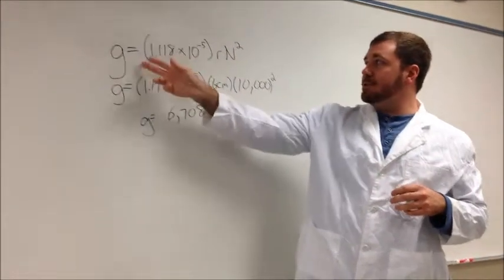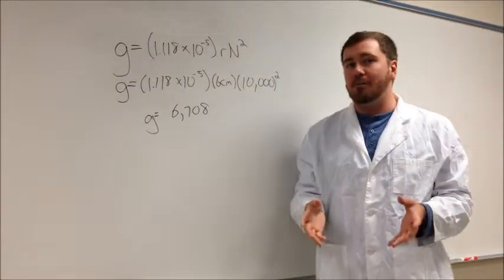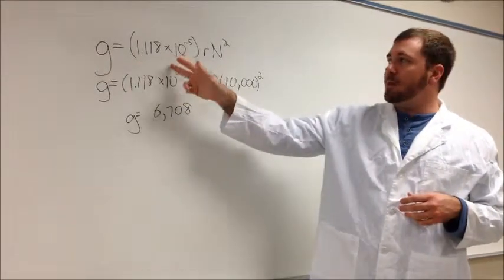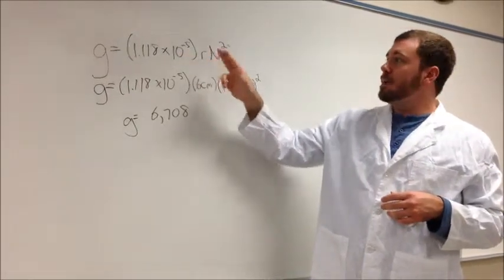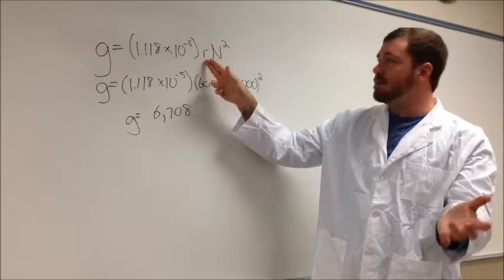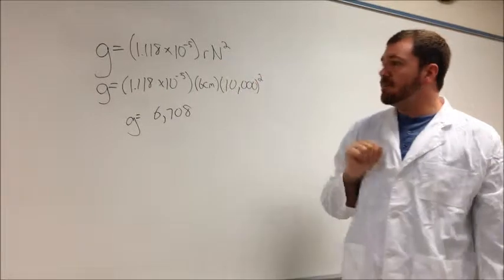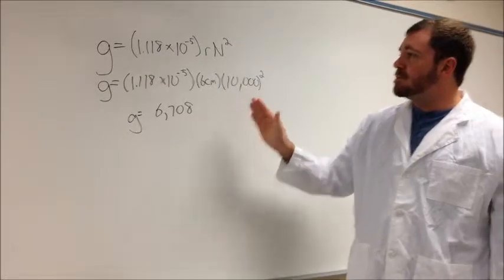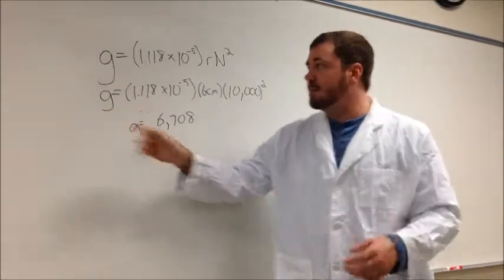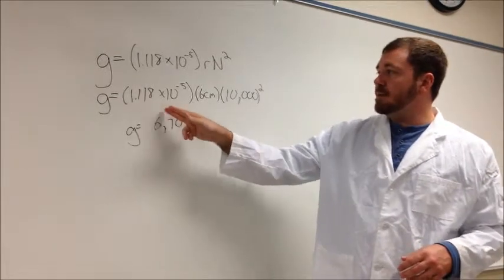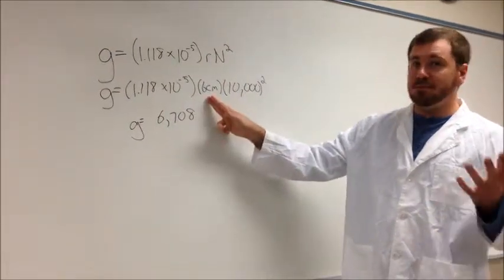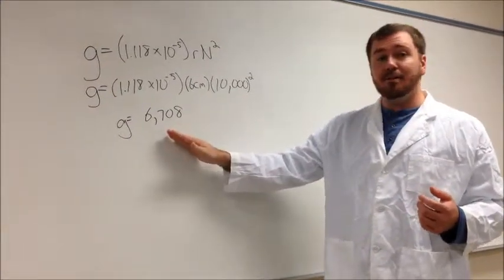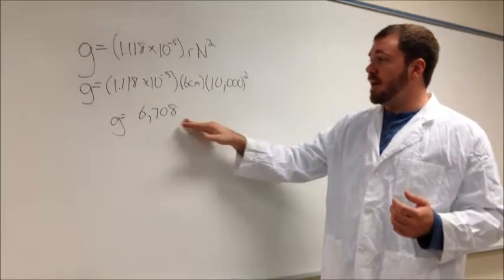So if you do have either times g or RPMs, you can actually solve for that other unknown. In this equation, you have times g equals 1.118 times 10 to the negative 5th times the radius, which is 6 in our case that you measured earlier, times the RPM squared. So let's say you're trying to find times g because your protocol says spin at 10,000 RPMs, but you only have a centrifuge that reads times g. So you times 1.118 times 10 to the negative 5th times the 6 centimeters, which is the radius in our case, times 10,000 squared. So the answer to that would be you can set the centrifuge to 6,708 times g.